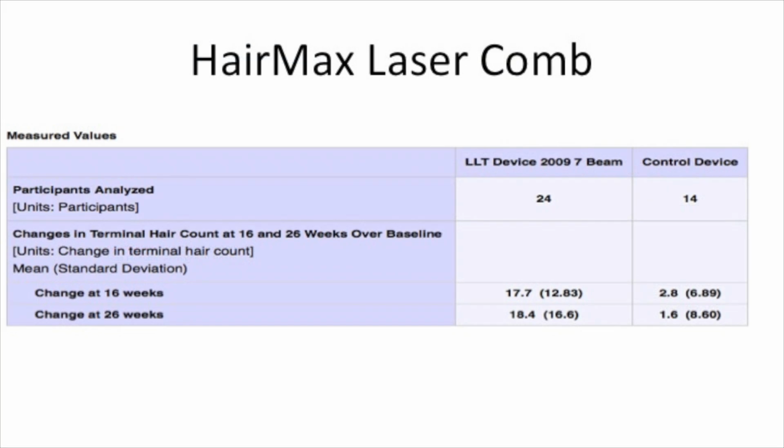This is, for example, a table that shows the results of their trial, which is probably not statistically significant considering the standard deviation, but nonetheless, it tells you what trials they did and what results they got in order to achieve approval. This is a very important benchmark for you to understand. While we can't be certain which of their trials was used for clearance, if they received approval with these results, it means you needn't do any better.